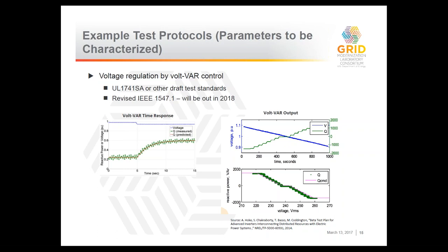Another very important thing when you are talking about grid services is that a grid service will always have a time component. When you are talking about frequency regulation or voltage regulation, in this case voltage regulation, it is how fast you can respond. The other thing is how good you can respond, which is shown in the next figure. In this case, you are running the inverter, changing the voltage, and measuring the output reactive power. As you can see, the reactive power response, this green curve, is not a continuous line but has small steps. That is why, as you said, in our model we need to have a ramp response. This is what I was mentioning: you have a limitation on how fast you can jump from one state to another.